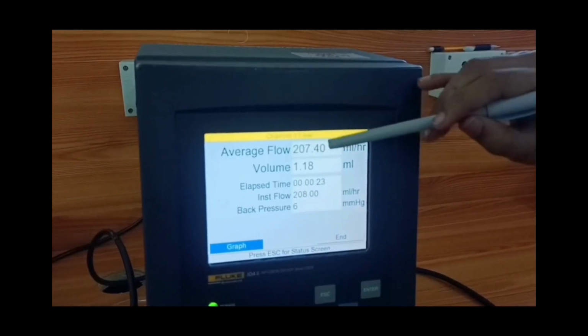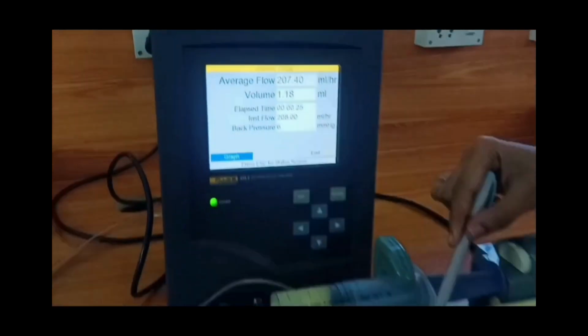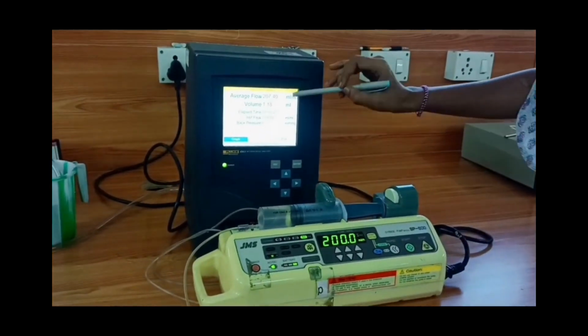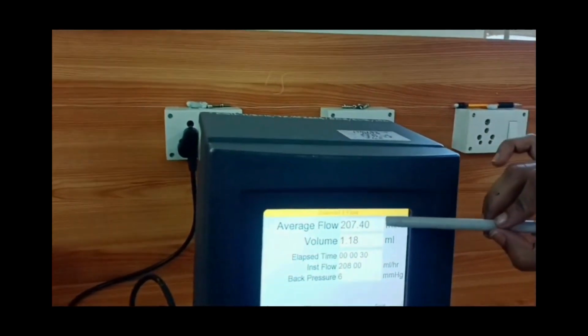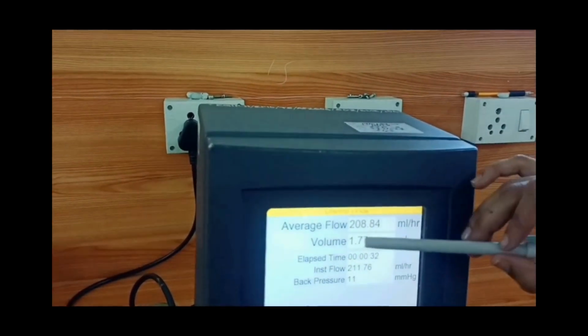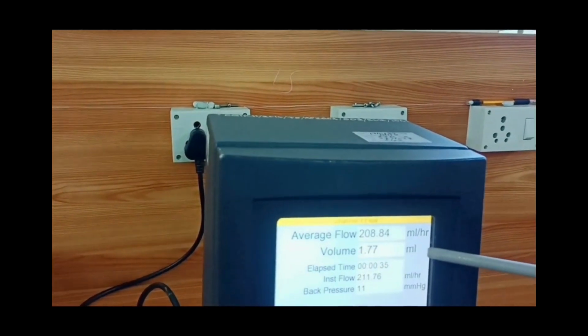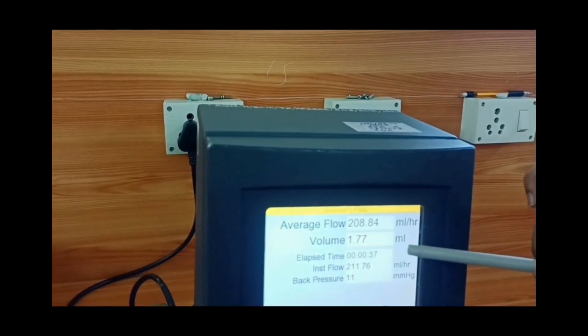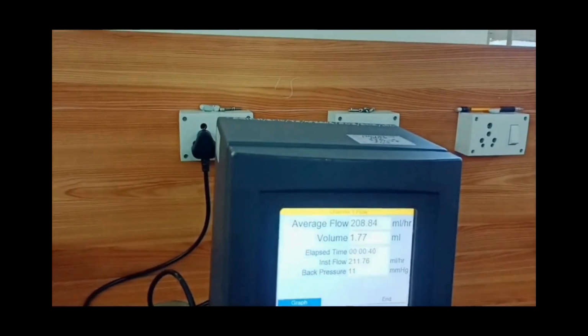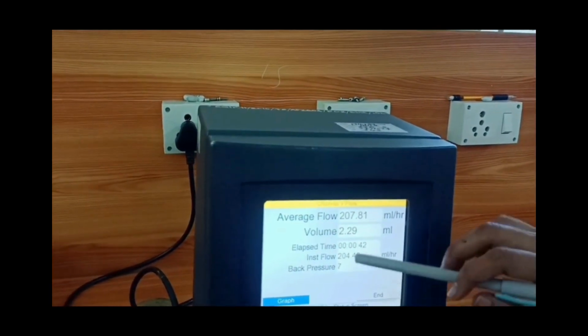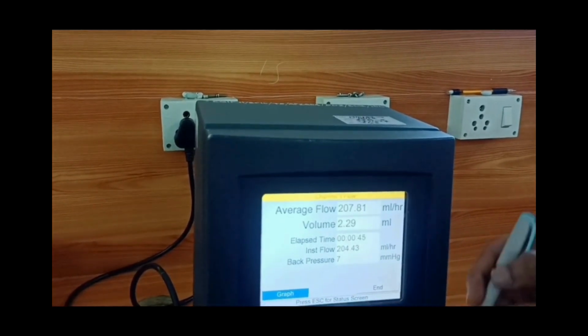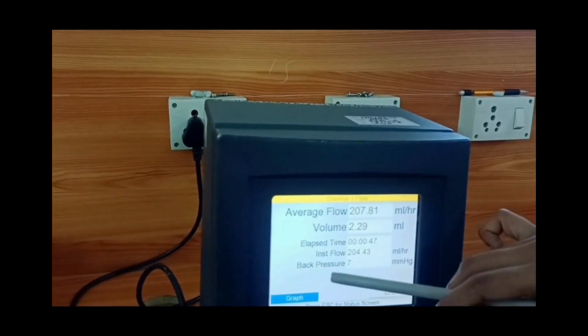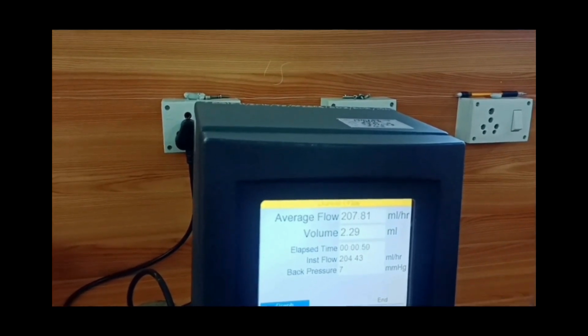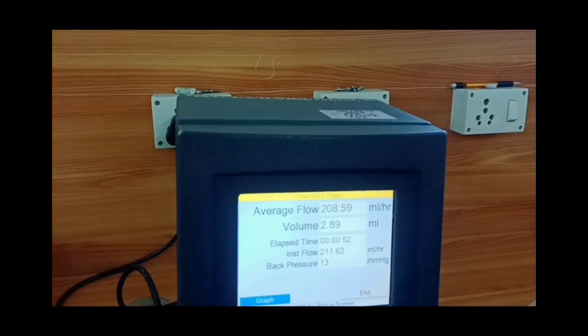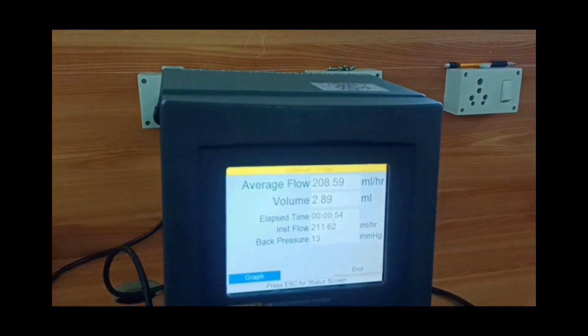The first one represents the average flow. Here we have set 200 ml per hour, and the same is represented here, but with plus or minus 5 error. Next is the volume in ml. Next is the elapsed time, like the time since we started the syringe pump. And next is the instant flow, like the flow rate at that particular instant. Back pressure is the resistance or force opposing the desired flow of fluid through the pipes, leading to friction loss and pressure drop. Now let us see the graph of this flow.